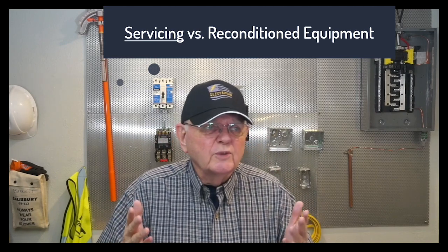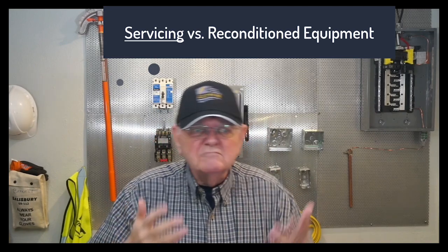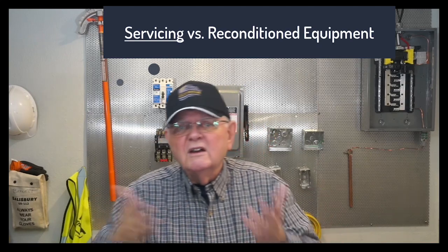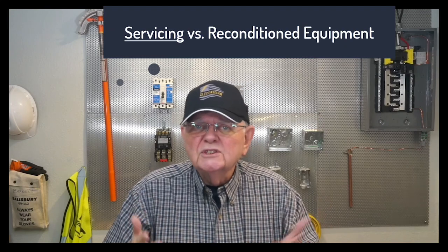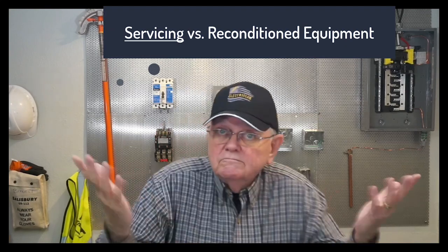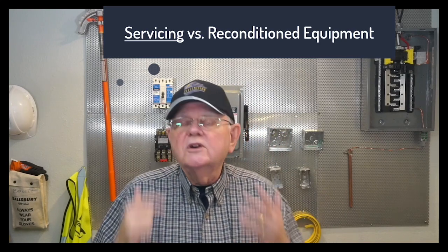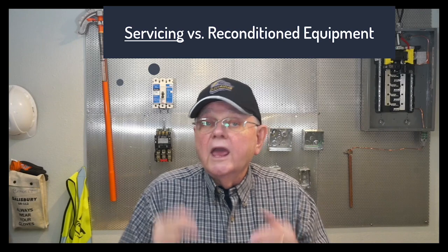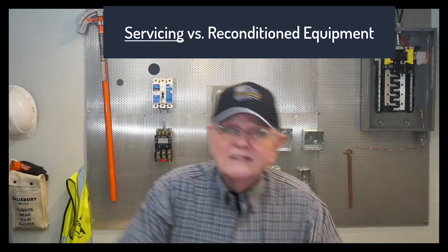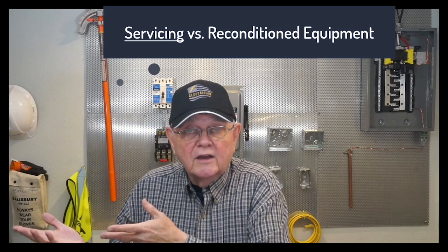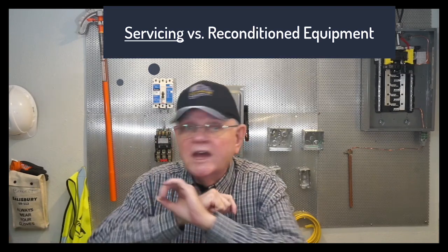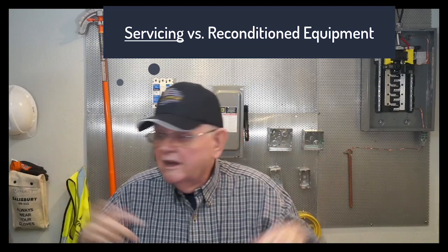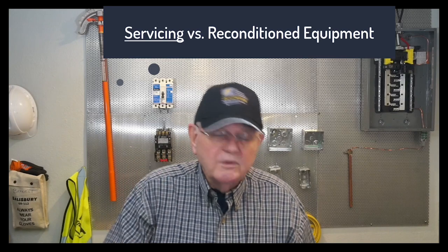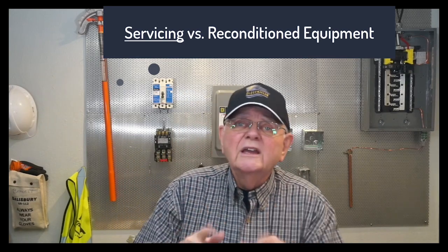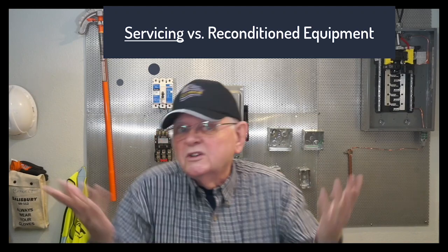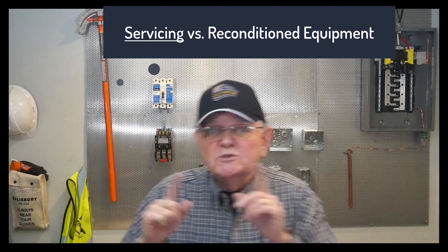Low voltage power circuit breaker. We rack it out, we inspect it, we do some tests on the contacts, we maybe lubricate, visual inspections and so forth, and maybe some secondary injection tests or whatever. Routine maintenance items, and then we rack it back in. As compared to taking that breaker out, sending it to a rebuild facility somewhere, and they completely tear down every stinking part on that breaker, don't they? And if something's getting worn, they replace it. They might replace springs and so on and so forth. So anyway, they completely rebuild that breaker and put it in like new condition, is the way I think of it. So the difference between reconditioned and servicing.